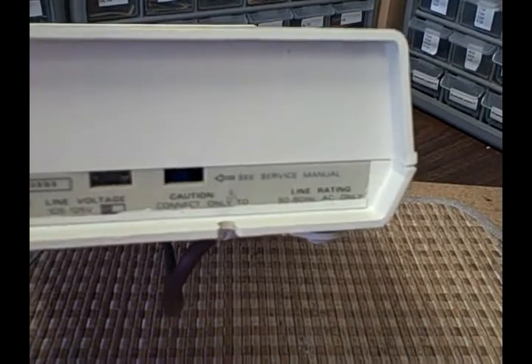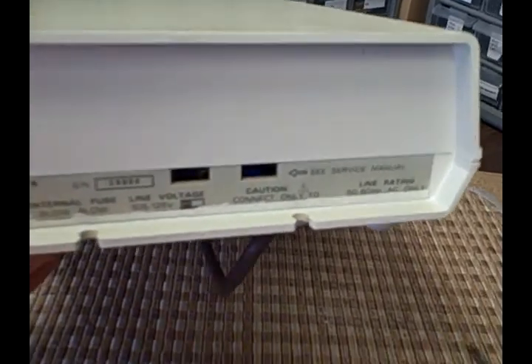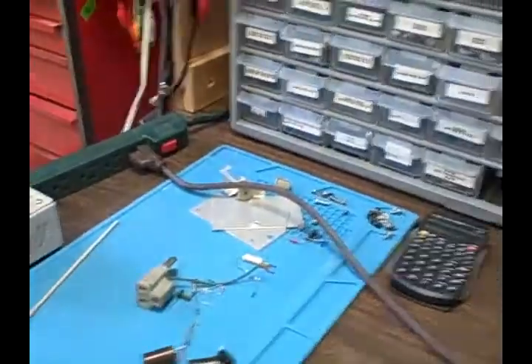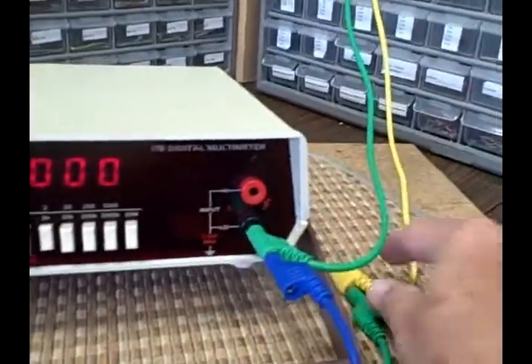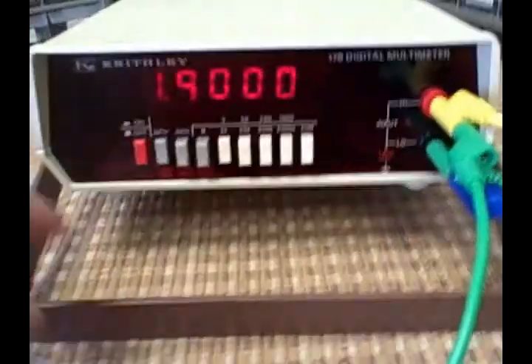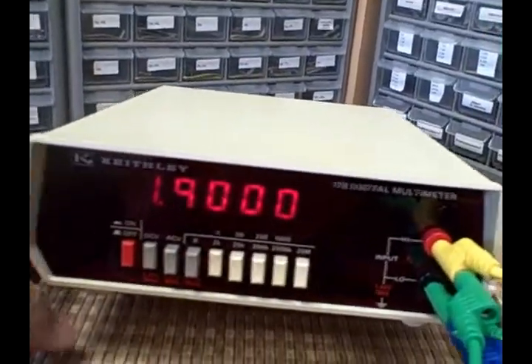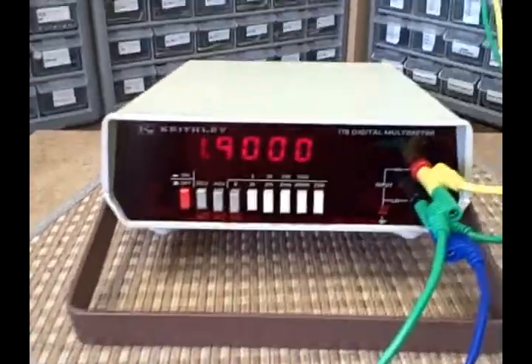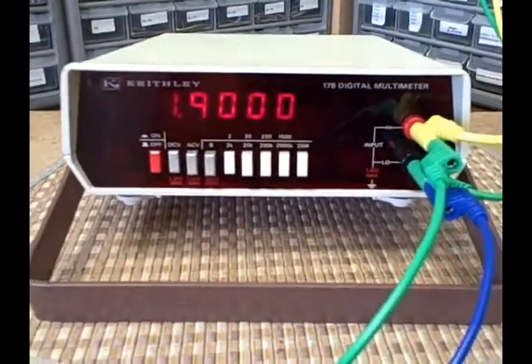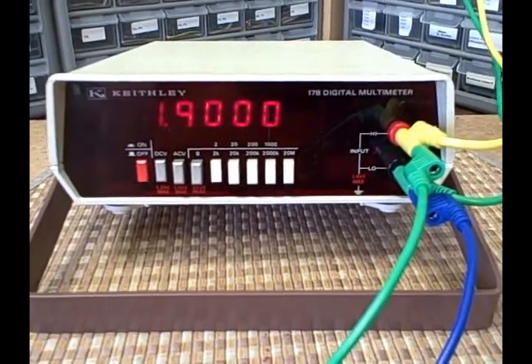And then in the back we have the line voltage and service manual and so on. And then we have a nice cord that goes into it. So we're going to use the verification sheets that come with the manual to verify the voltages that we obtain on the ranges, and that they're within the calibration limits. So give me a minute, we'll get started.